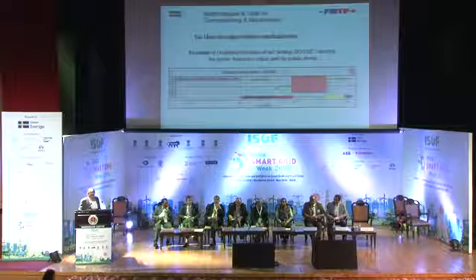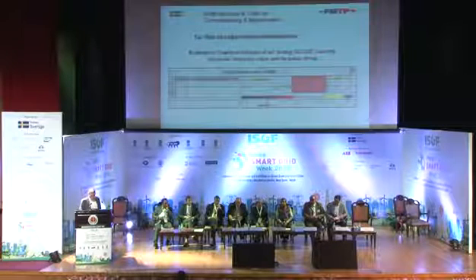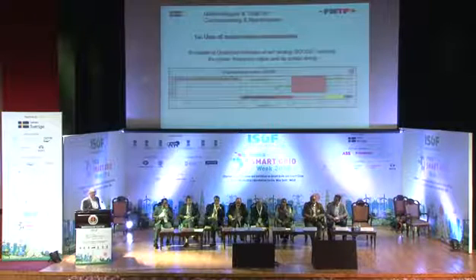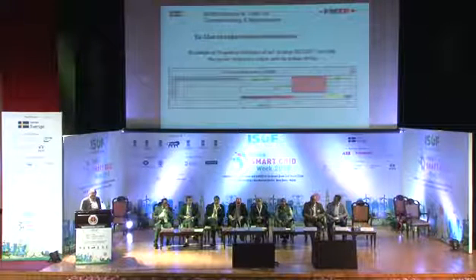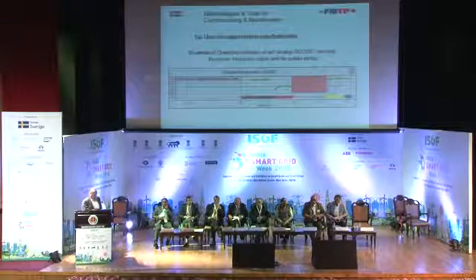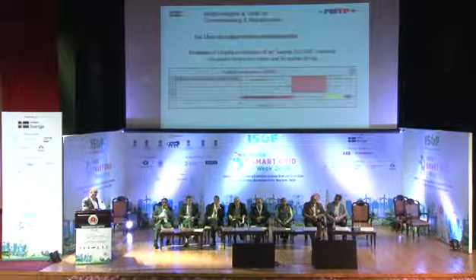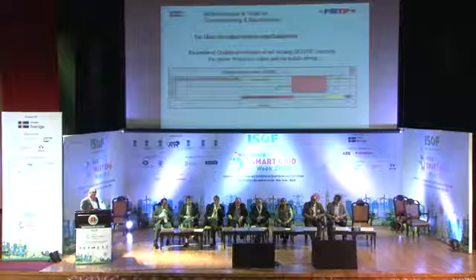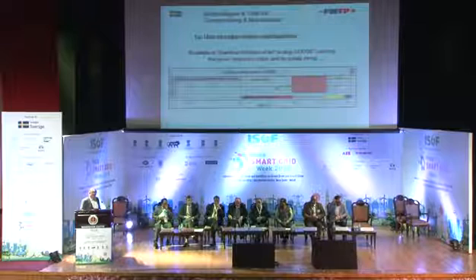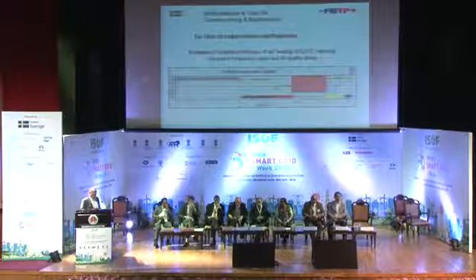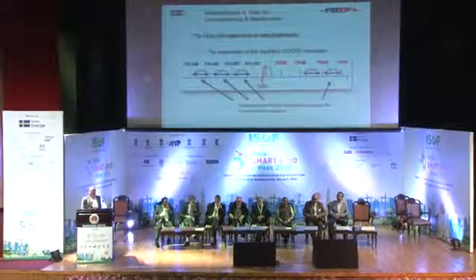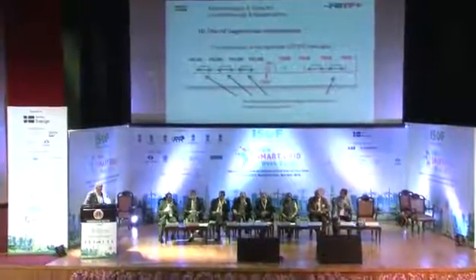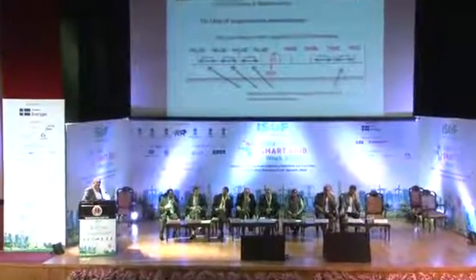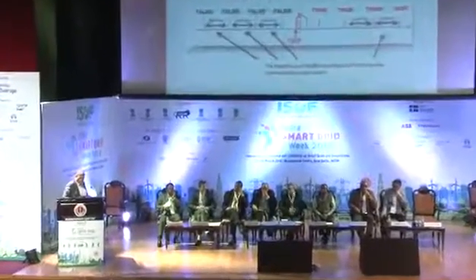We can also, by supervision, graphically show this. Here we have a Goose with a frequency, 50 Hertz frequency, and we can see that when there is something wrong going on, the quality, shown by the black line which is correct when it's black, changes into different colors depending on the different errors accessible from the quality string. Another mechanism that is important here is the repetition of information and the supervision of that repetition.